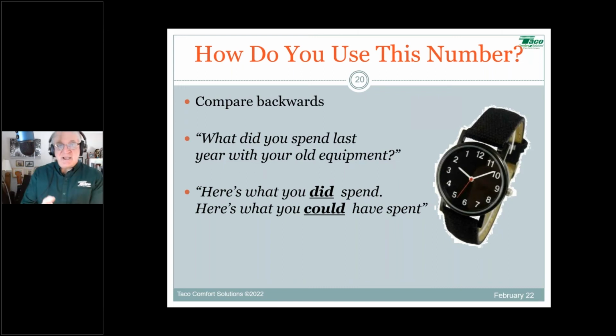Now, for that, if you're going with ECM circulators, you also have to factor in the annual savings of electricity, which is a pretty standard formula. You can do that using that 2,500 hours, and depending upon your kilowatt rate, it could be anywhere from 28 to 40 bucks a year per circulator. So if you have 3 or 4 circulators, let's say 30 bucks times 3 circulators, that's another $90 per year that you're saving. So you factor all of that in.